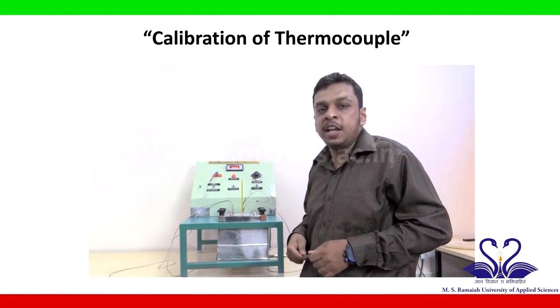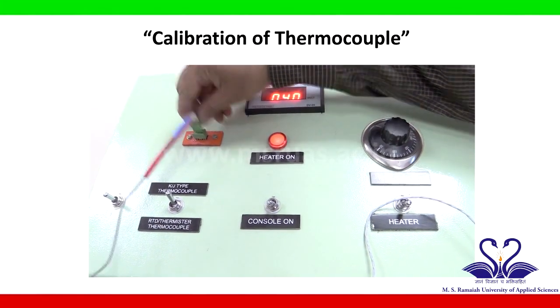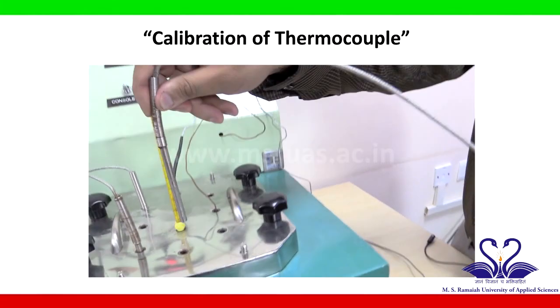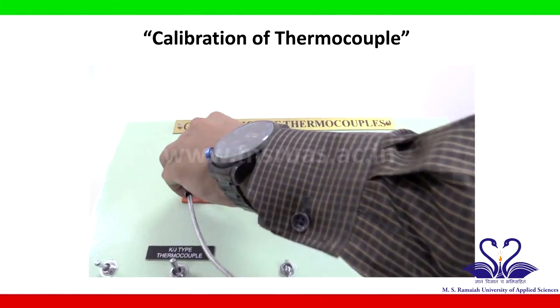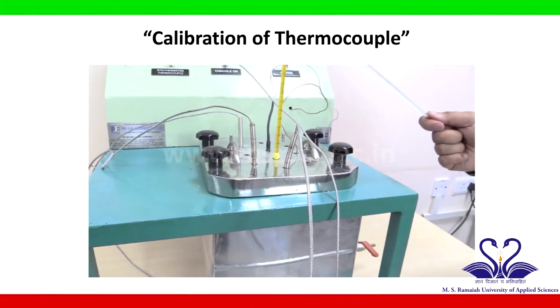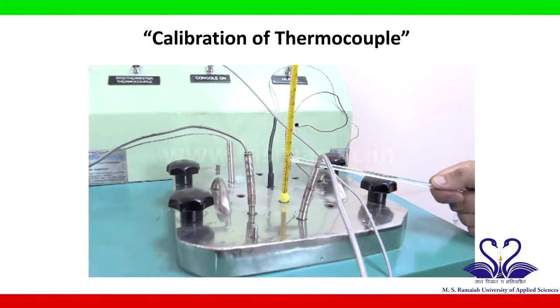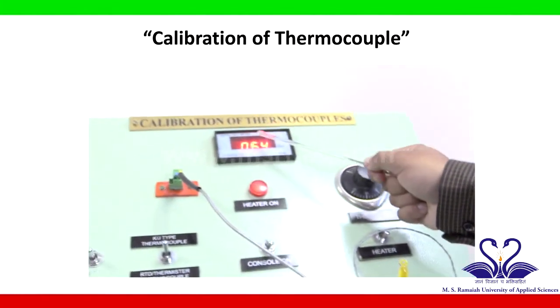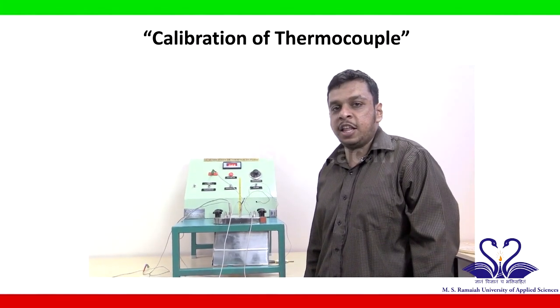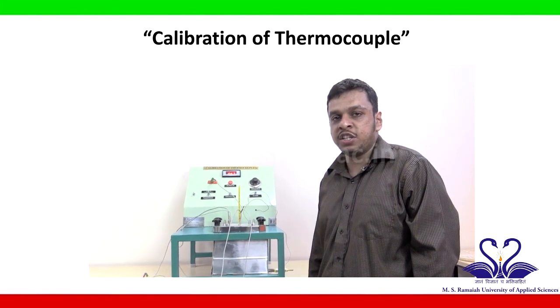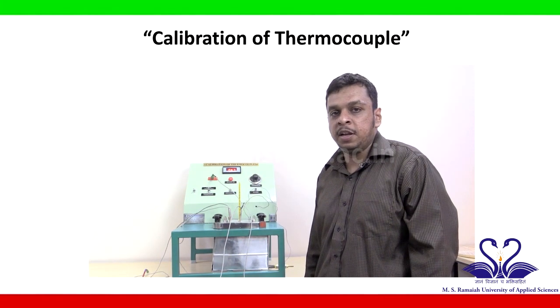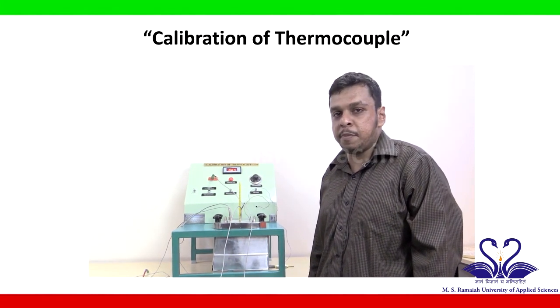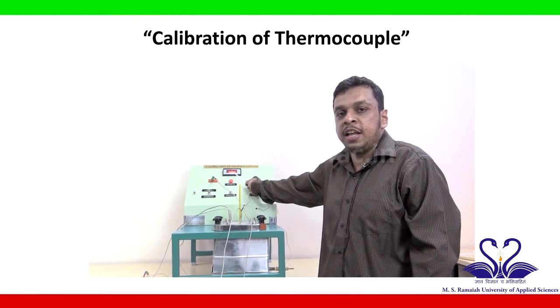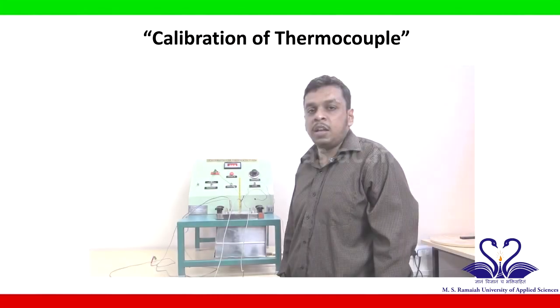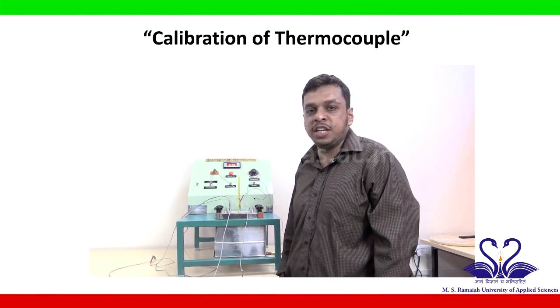Next, we are going to calibrate J-type thermocouple. Remove the K-type thermocouple and now connect the J-type thermocouple. Now take down the values for temperature of J-type thermocouple with its corresponding voltage. Now calculate the theoretical possible temperature and voltage combinations using the standard formula for J-type thermocouple. It is important to note that in this particular experiment, the voltage being displayed in the digital screen is in terms of millivolts. Now we have completed the calibration of K-type and J-type thermocouples.